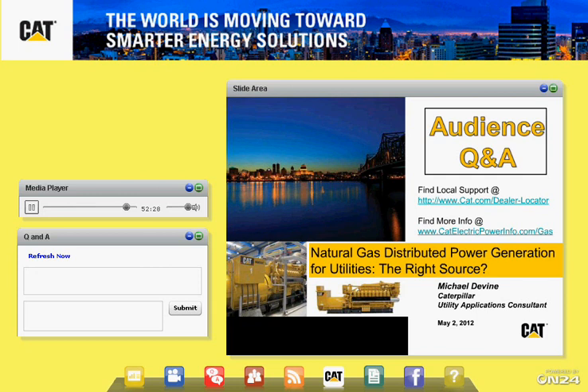Yeah, most of the life safety devices are going to be diesel in nature. It's not common to have gas, because most life safety applications require on-site fuel sources. And so that may be problematic, to have enough fuel to run a large natural gas system in particular for extended periods of time. If it's 100 kW or 200, a propane system or even an LNG or CNG type system may work. But it's more common that you're going to see diesel resources in life safety.